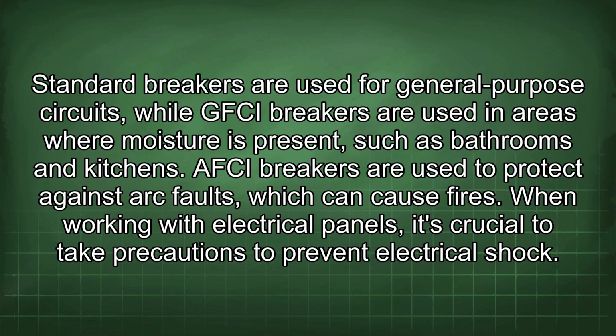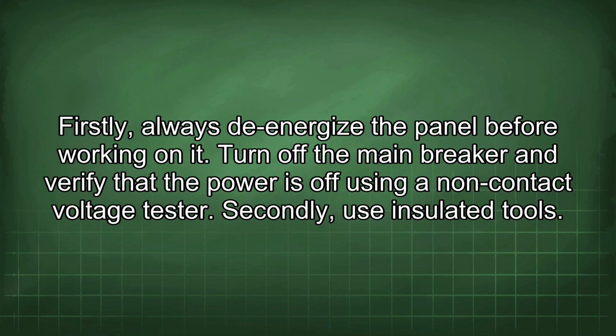AFCI breakers are used to protect against arc faults, which can cause fires. When working with electrical panels, it's crucial to take precautions to prevent electrical shock. Firstly, always de-energize the panel before working on it. Turn off the main breaker and verify that the power is off using a non-contact voltage tester.